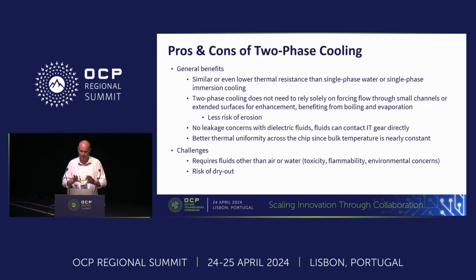They're putting memory modules close to logical processing modules. Memory modules typically have lower flux but also a lower temperature requirement. So where thermal designers normally want to bring their coldest fluid to the hottest portion of a chip, they're challenged because that fluid is then too warm to cool the lower-flux components with lower temperature limits. In a two-phase cooling approach, we always boil at the saturation temperature, so no matter what type of module, you're ultimately sinking heat to the same temperature.